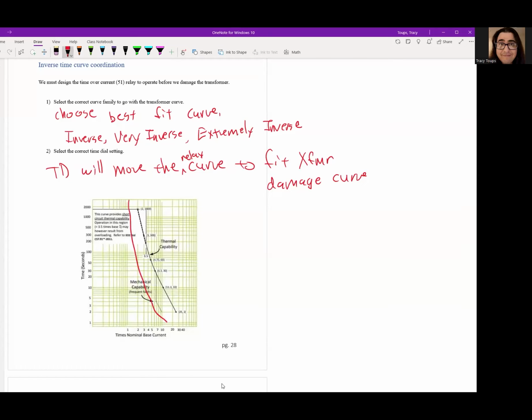Something like that. That's not too bad. So that's our curve, and you'll choose a time dial down the curve. Notice that the curve is lower and to the left, and it barely scrapes by the mechanical capability curve. So we're covering that. Well, we fully covered the thermal capability curve as well. Okay.